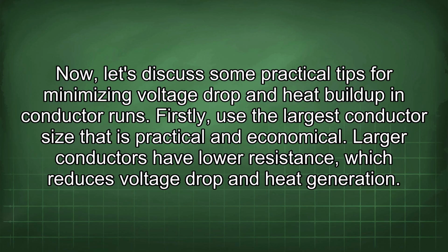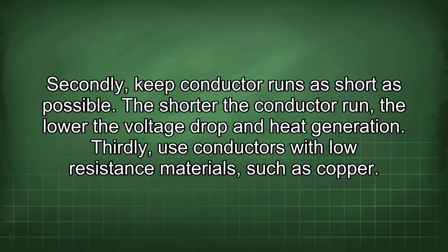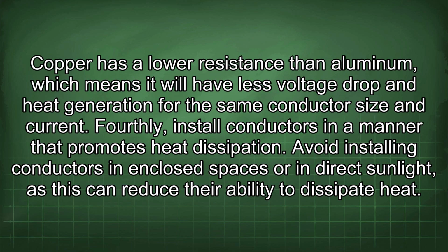Now let's discuss some practical tips for minimizing voltage drop and heat buildup in conductor runs. Firstly, use the largest conductor size that is practical and economical. Larger conductors have lower resistance, which reduces voltage drop and heat generation. Secondly, keep conductor runs as short as possible. The shorter the conductor run, the lower the voltage drop and heat generation. Thirdly, use conductors with lower resistance materials, such as copper. Copper has a lower resistance than aluminum, which means it will have less voltage drop and heat generation for the same conductor size and current.